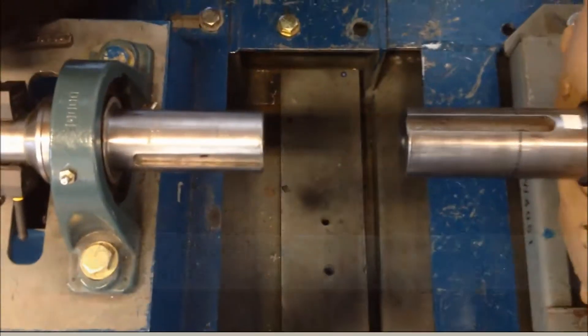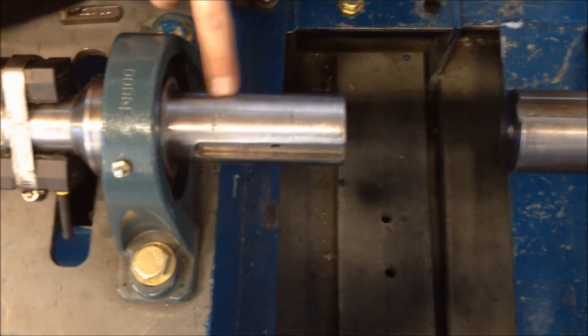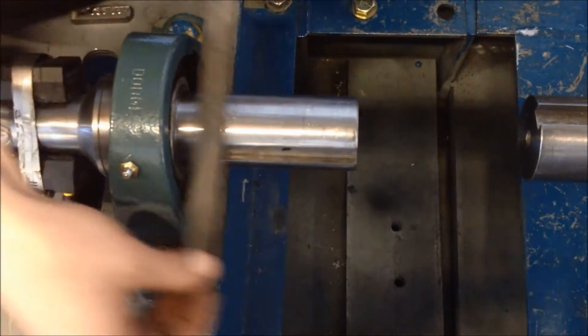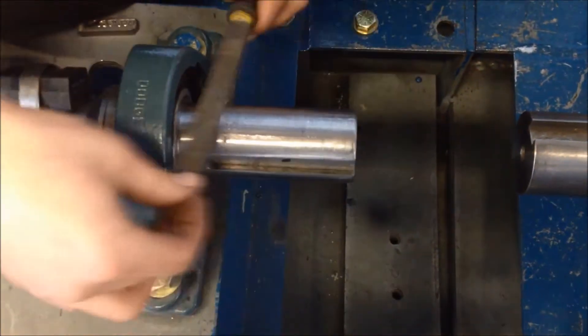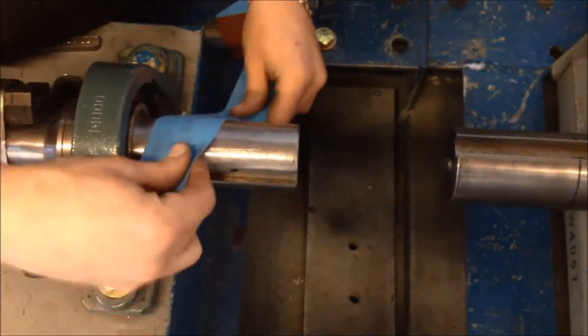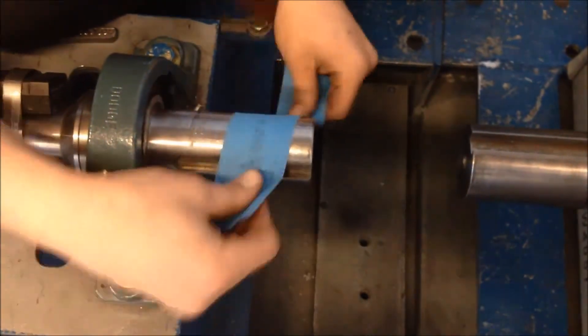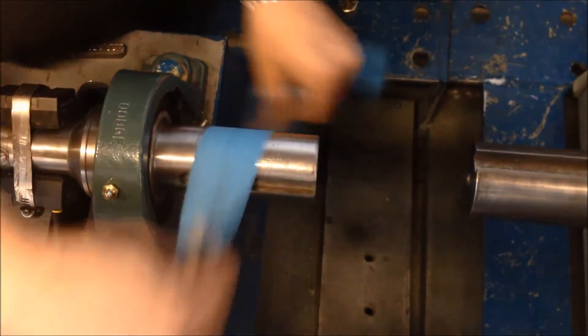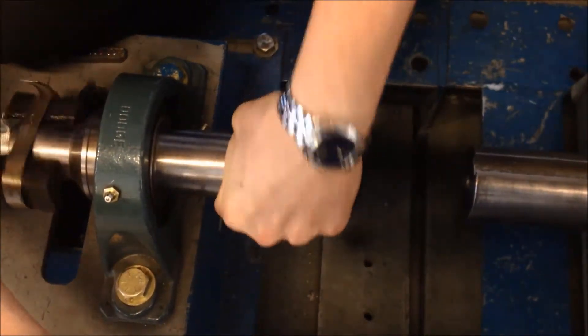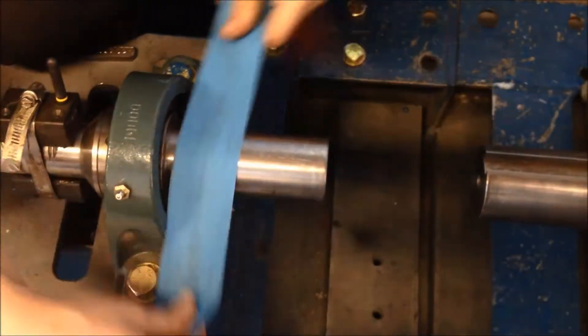Shaft Preparation. Prior to installing the FSC, it is important to make sure both motor and load shafts are in good condition. Use a fine file to smooth out any dings or dents in the shaft. Use fine emery cloth or sandpaper to remove any paint or rust from both shafts. It is important that the shafts are clean and free of any defects.